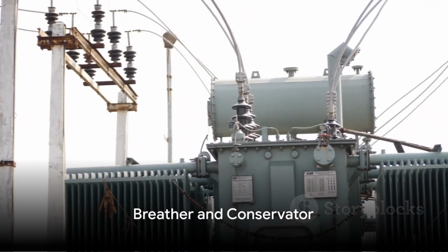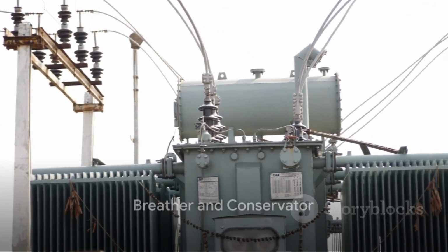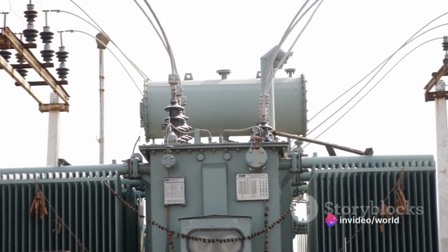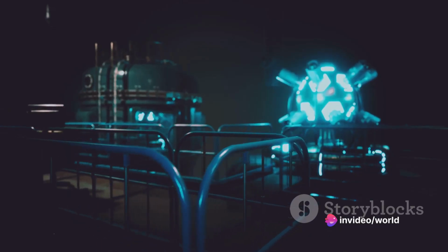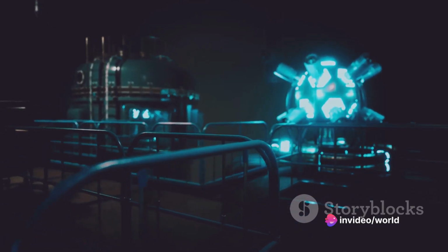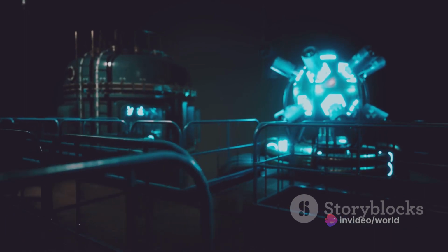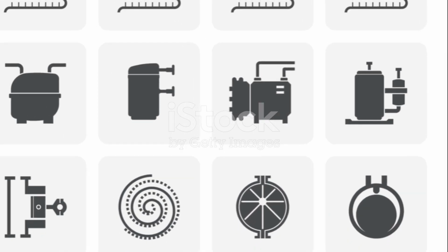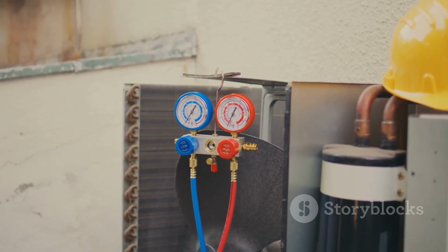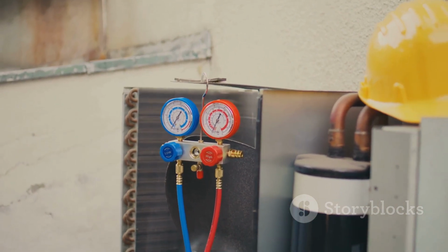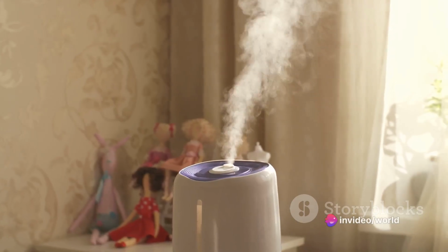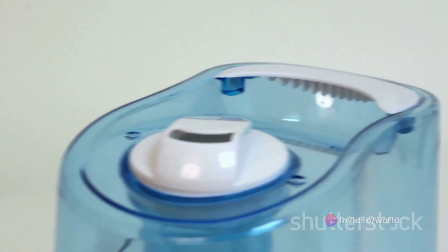Last, but not least, let's talk about the transformer's lungs and oil regulator, the breather and conservator. The breather, an often overlooked component, plays a vital role in the longevity of a transformer. It regulates the air inside the transformer and, most importantly, prevents moisture from entering. Picture this, it's like a gatekeeper using desiccants to absorb moisture from the incoming air, thereby ensuring a dry and healthy environment for the transformer.